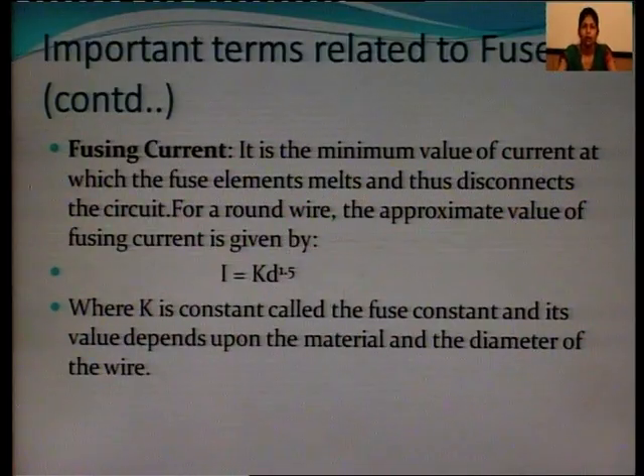Now next is fusing current. It is the minimum value of current at which the fuse element melts and thus disconnects the circuit. For a round wire, the approximate value of fusing current is given by I equals K D to the power 1.5, where I is the current, K is the fuse constant whose value depends upon the material and diameter of the wire, and D is the diameter of the wire.